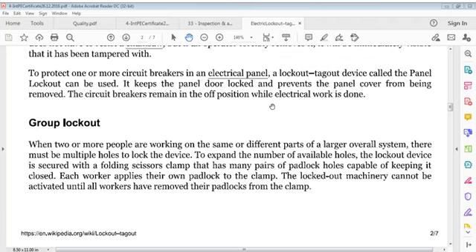When two or more workers work on the same or different parts of a larger overall system, there must be multiple holes to lock the device. To expand the number of available holes, the lockout device is secured with a folding scissors clamp that has many pairs of padlock holes capable of keeping it closed. Each worker applies their own padlock to the clamp. Locked out machinery cannot be activated until all workers have removed their padlocks from the clamp.